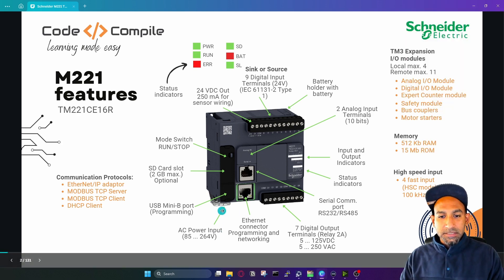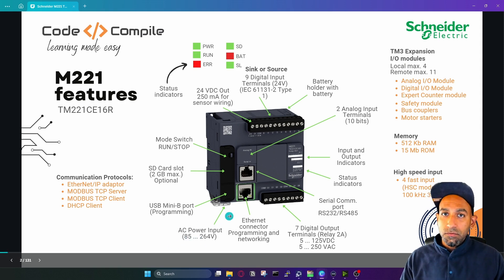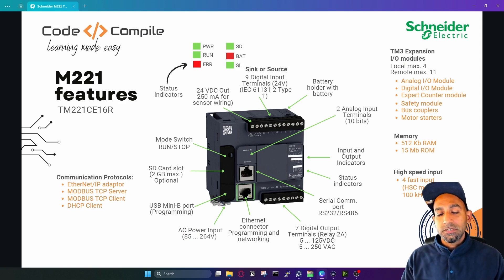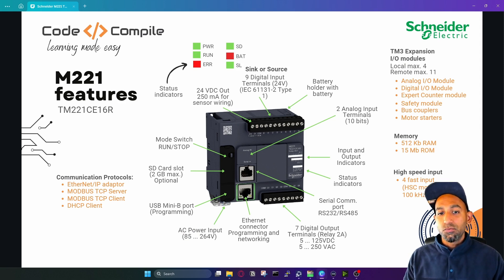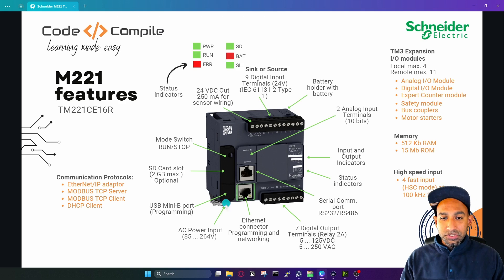This PLC is powered by AC input with a range from 85 to 264 volts. You don't need a separate DC power supply — it has a DC converter inside which converts from AC to DC. So you just need to connect your AC supply.